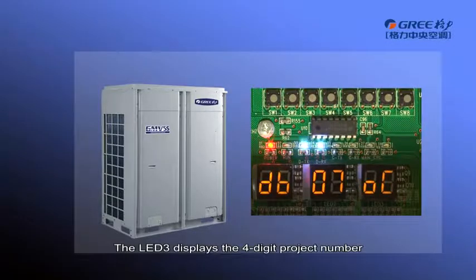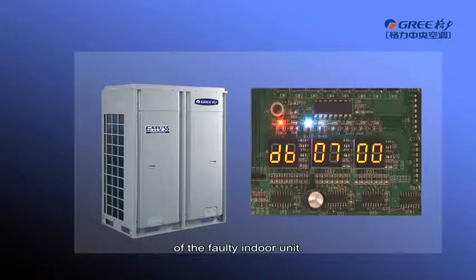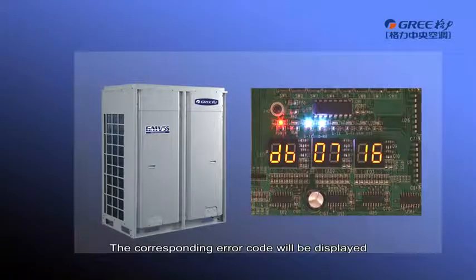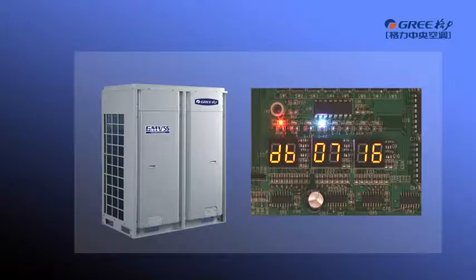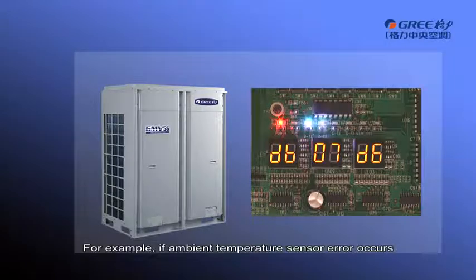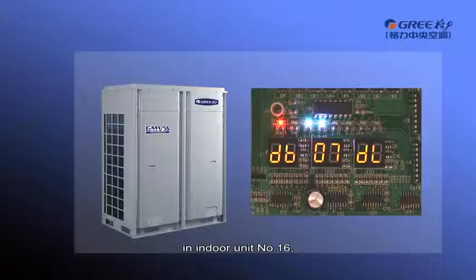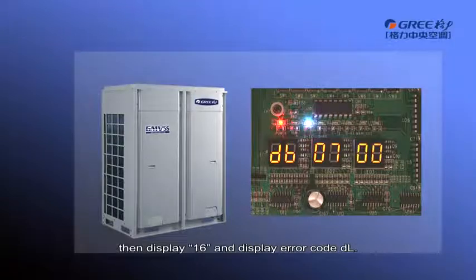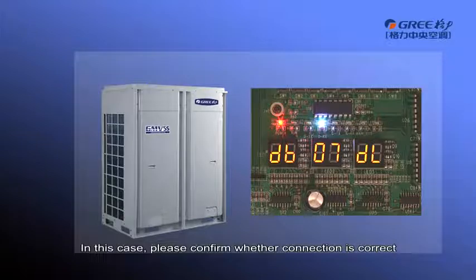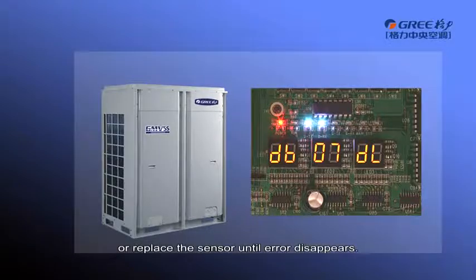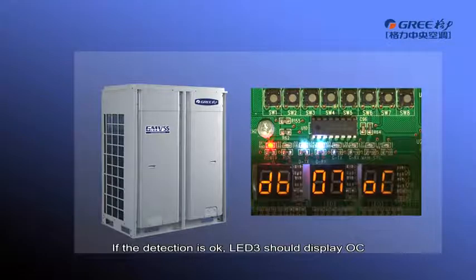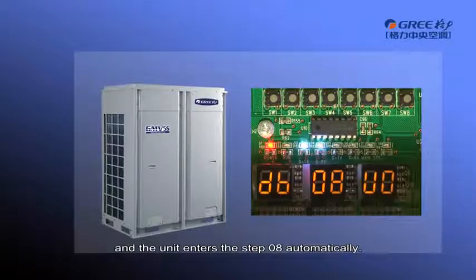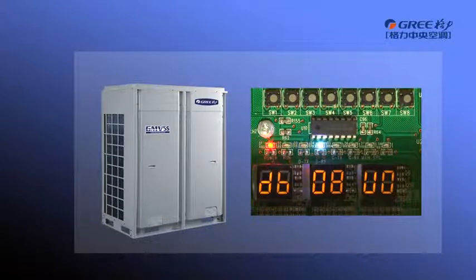The LED 3 displays the 4-digit project number of the indoor unit. The corresponding error code will be displayed after 3 seconds. For example, if ambient temperature sensor error occurs in indoor unit number 16, LED 3 will display 00 first and then display 16. And display error code DL. In this case, please confirm whether connection is correct and replace the sensor until error disappears. If the detection is OK, LED 3 should display OC and the unit enters the Step 8 automatically.